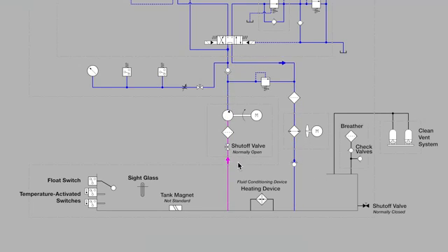Let's move over to the pump assembly, and perhaps we should draw attention to a line with the occasional dash in it. Whenever we see those lines, it lets us know that this group of symbols that is within it are all mounted together on the same physical assembly. So we see a shutoff valve from the tank towards the pump, but before we make it to the pump, we see something called inlet line filtration, which in some regard is a form of straining to filter out large contaminants before they enter the pump, but is not exactly like a strainer in the tank.